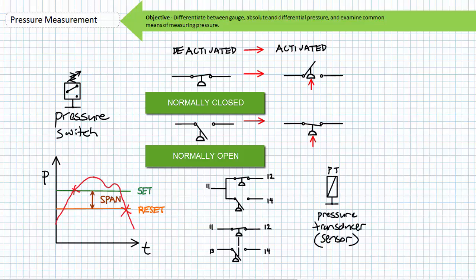Pressure switches, it should be noted, are binary in nature, meaning they can be placed in one of two mutually exclusive states, either open or closed, and never a little bit of both or halfway in between. Pressure sensors, in contrast, measure the distortion of the disk and output an electrical voltage or current signal proportional to the amount of distortion. Pressure sensors are sometimes known as pressure transducers and differ from switches in that they are also analog pressure measurement devices. More pressure means more electrical signal.